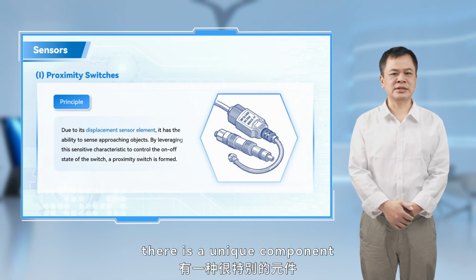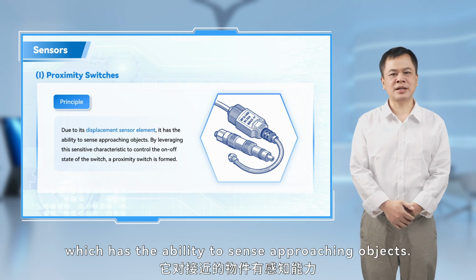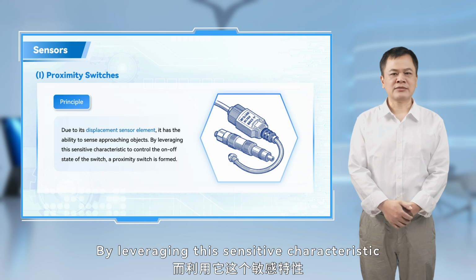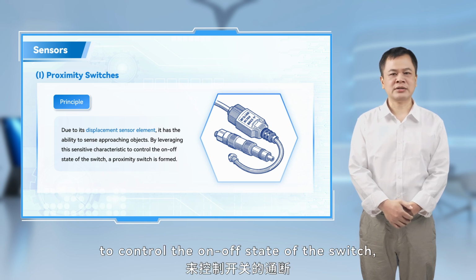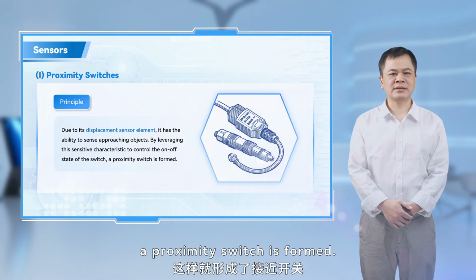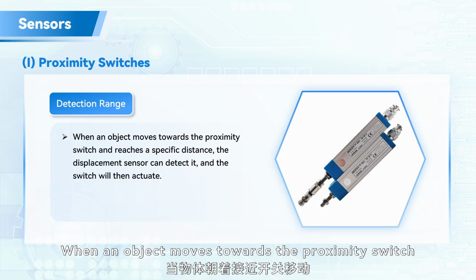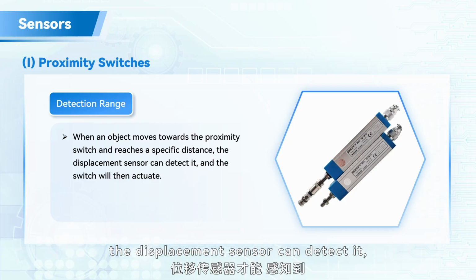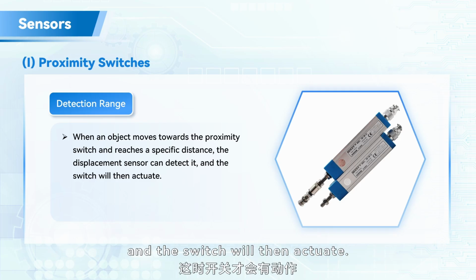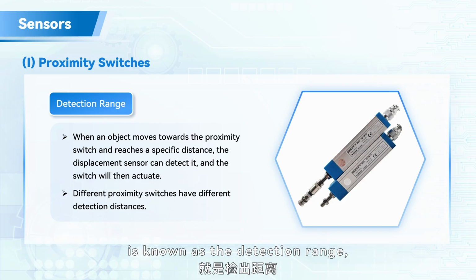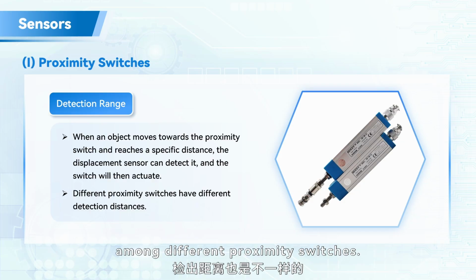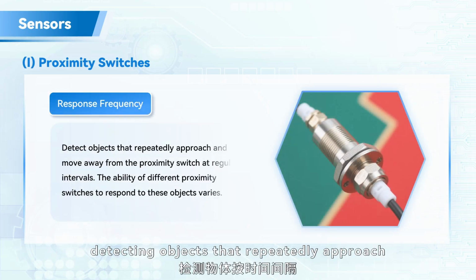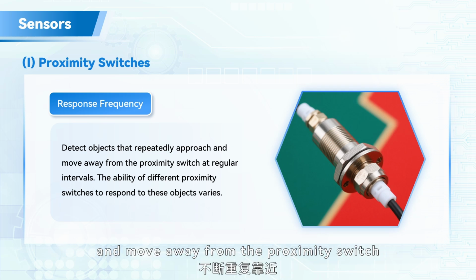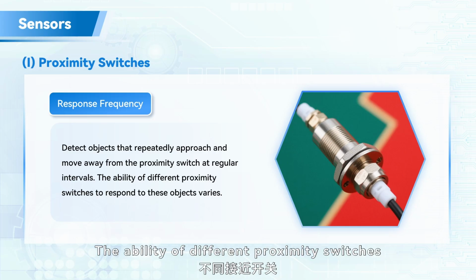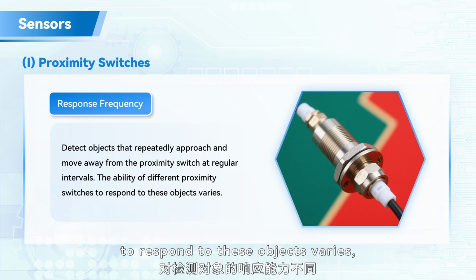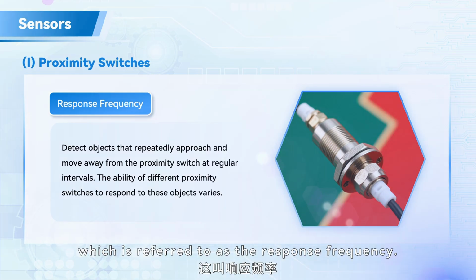Among various switches, there is a unique component called a displacement sensor, which has the ability to sense approaching objects. By leveraging this sensitive characteristic to control the on-off state of the switch, a proximity switch is formed. When an object moves towards the proximity switch and reaches a specific distance, the displacement sensor can detect it, and the switch will then actuate. This specific distance is known as the detection range, which varies among different proximity switches. Another scenario involves detecting objects that repeatedly approach and move away from the proximity switch at regular intervals. The ability of different proximity switches to respond to these objects varies, which is referred to as the response frequency.